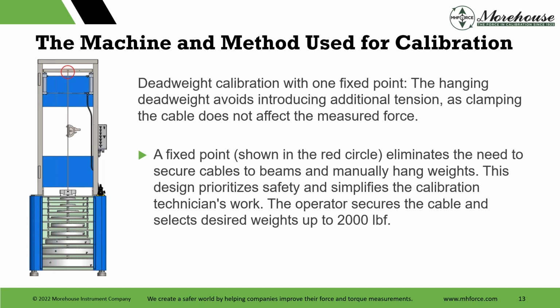So dead weight calibration, highlighted here. You see this, 1 fixed point. This is a drawing of our dead weight cable tensiometer. 1 fixed point, tensiometers clamped, weights just float in the air. So this eliminates the need to secure cables to beams and manually hang weights. The design also prioritizes safety and simplifies the calibration technician's work. Operator secures the cable and selects the desired weights up to 2,000 pounds. They can just flip a switch, the weight's applied.